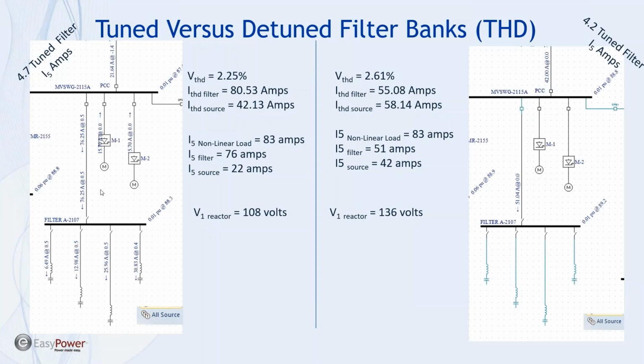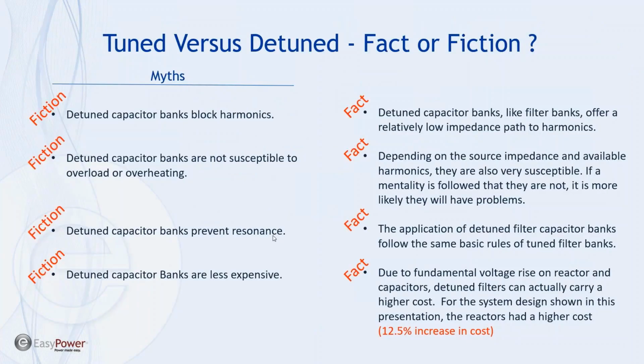So at the fifth harmonic, even though this is much closer tuned to the fifth harmonic, the difference between tuned versus detuned is not significant, only 25 amps. So if you think about what's going on here, there is not a lot of benefit from the reactor standpoint and the capacitor bank standpoint in going to 4.2 versus 4.7. What have we really saved here? Not a whole lot. And that's really a key point of this presentation.